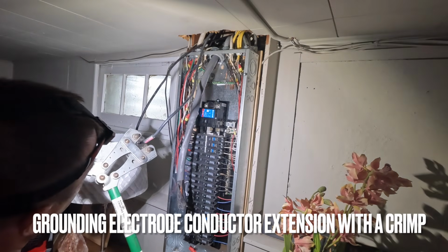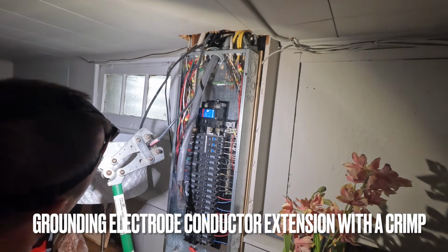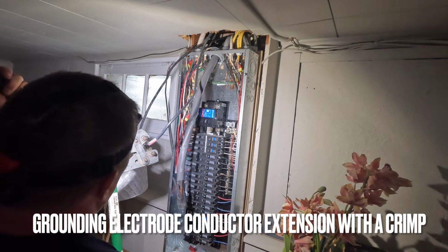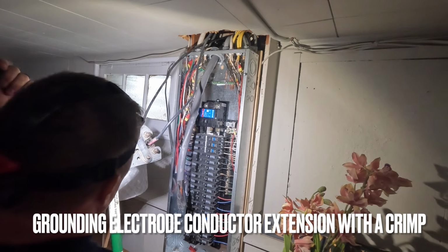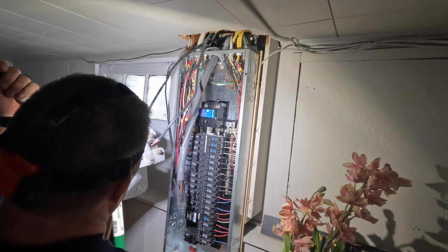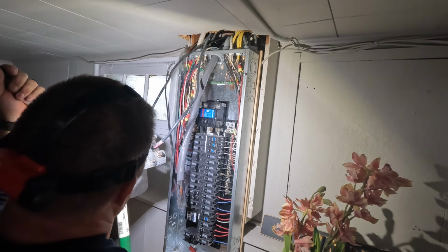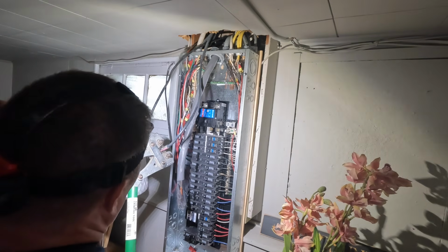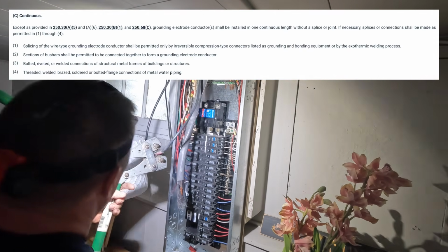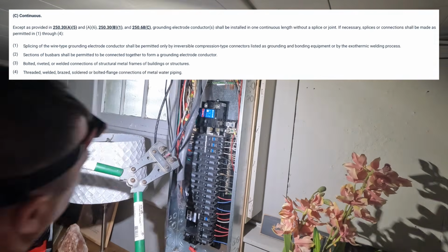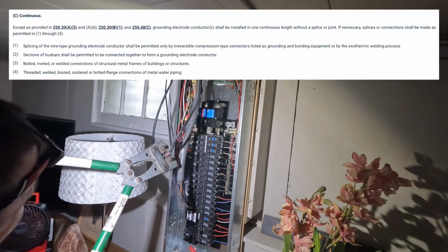So here you have 2 choices. You can either extend the grounding electrode conductor as I'm doing here with an irreversible crimp, or run a whole new grounding electrode conductor. You cannot splice this with a wire nut or a split bolt. It must be extended using an irreversible crimp, which is what this is here.